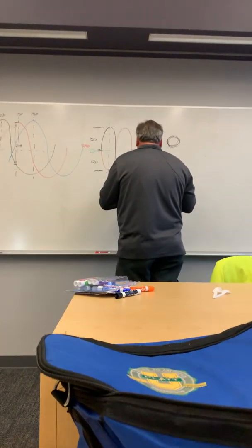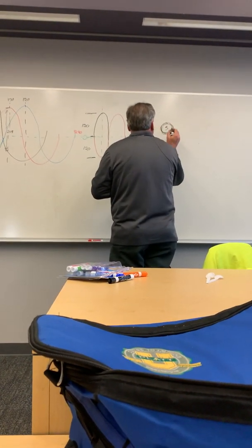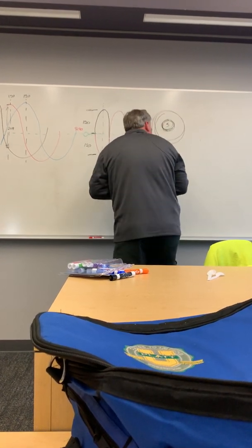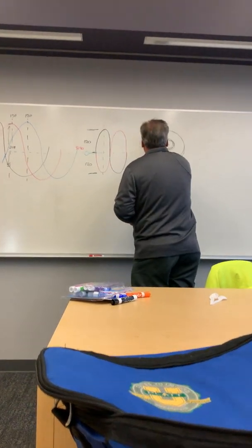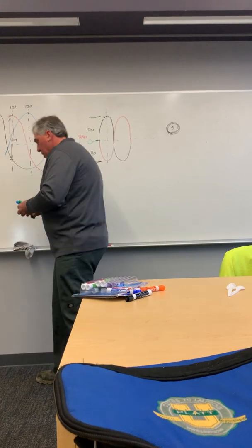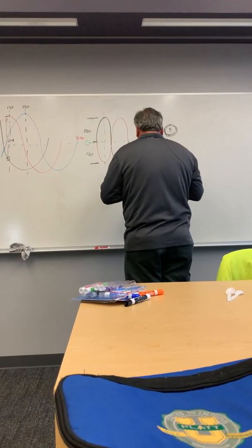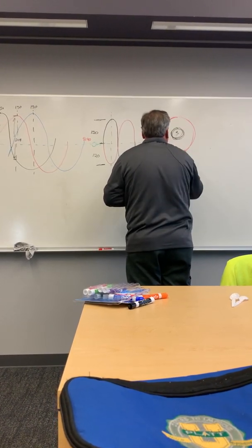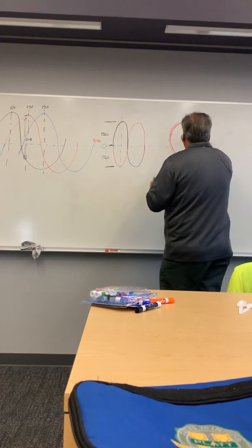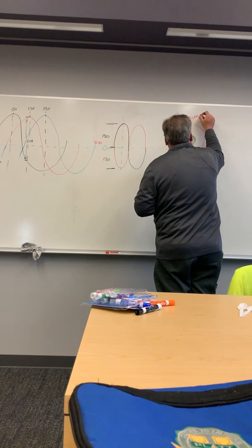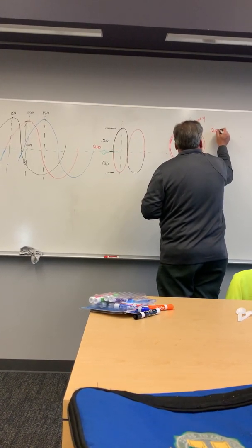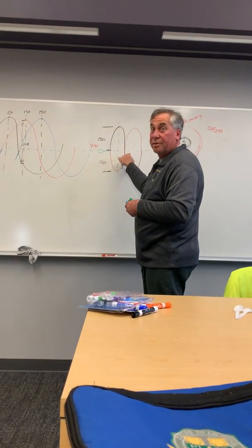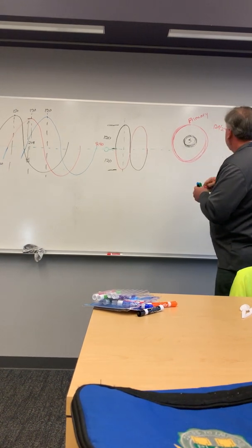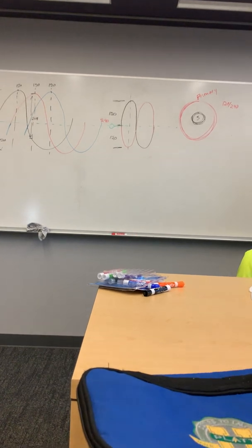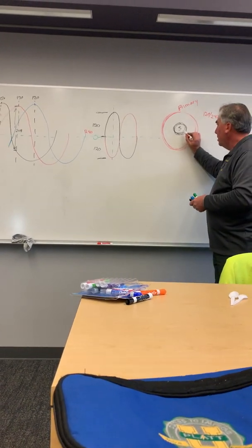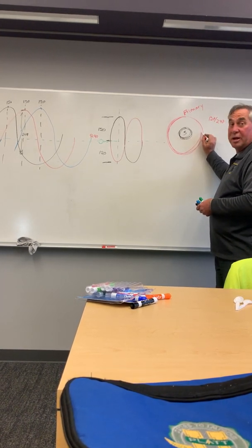So now we have what I think is the secondary windings. If we go outside we'll see the generator, and if we open up one of the transformers, it has two sets of windings - we'll call this the primary. Say we've got 120, 240 - a simple transformer would look like this. Now this 240, what is that ratio? That's 2 to 1, so there should be twice as many secondary windings as primary windings.